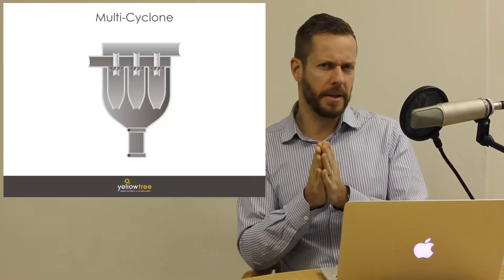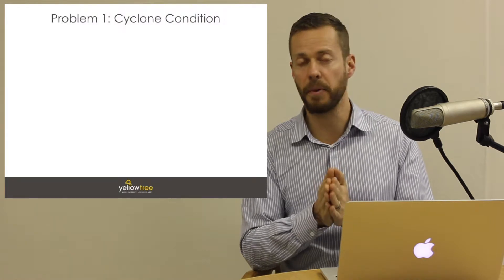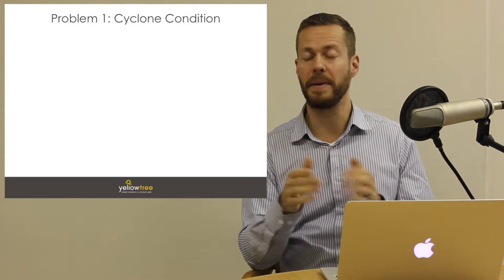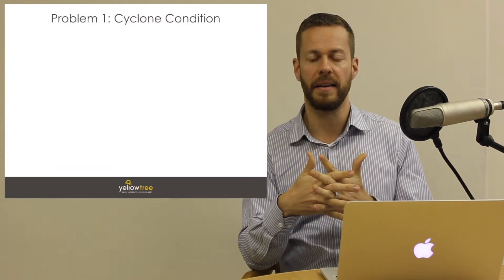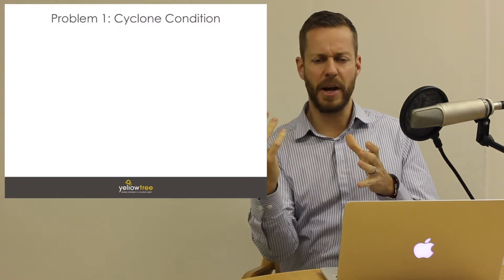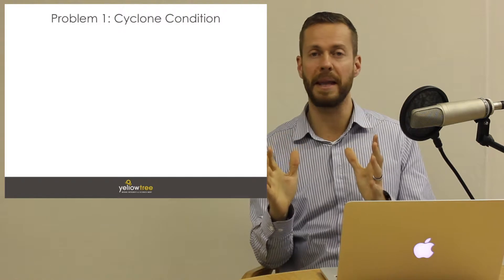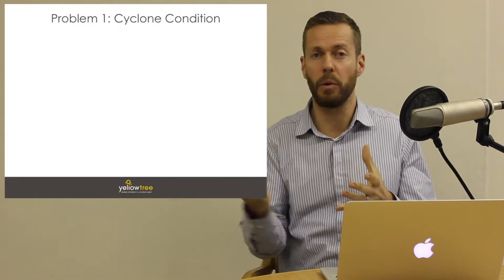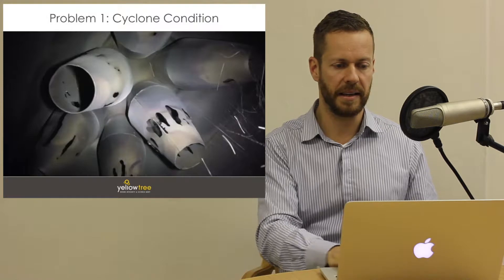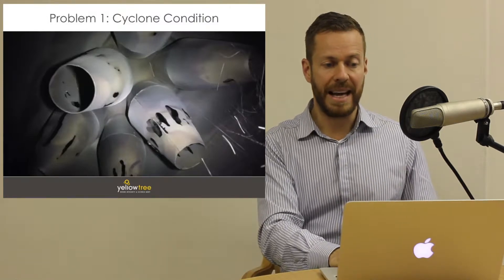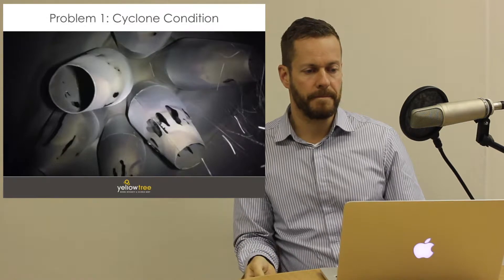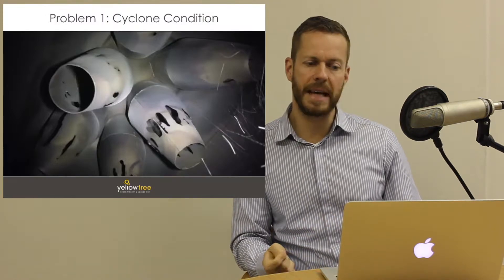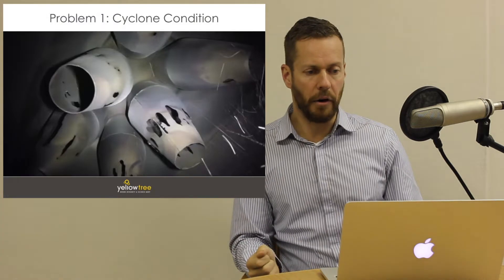There are five problems with multicyclones to discuss. The first is the most simple: most multicyclones have not been opened up in 20 or 30 years, and they are eroded inside. The very nature of the separation process — spinning abrasive particulate matter inside a metal body all day — wears down the cyclones. As shown in the video clips, individual cyclones are often in very poor condition; some are completely eroded away entirely.